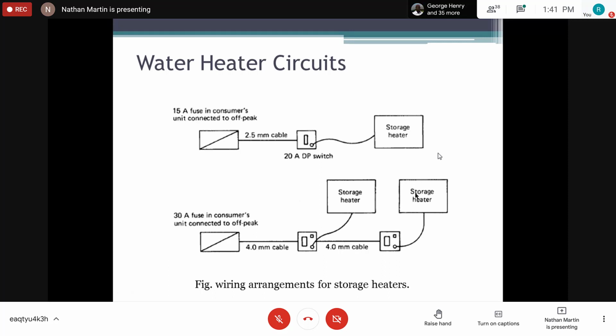Now, why would we want to put two water heaters on one breaker? It can be a case that we have two small water heaters supplying different sections of a building, right? In this case, rather than running separate cable, we buy a larger cable and we are able to supply the two water heaters.